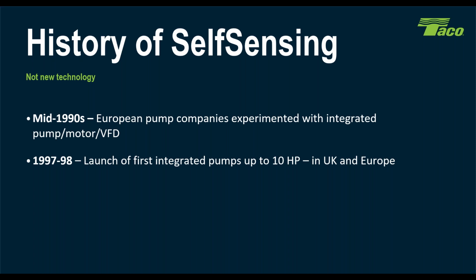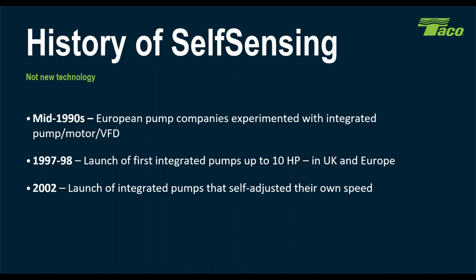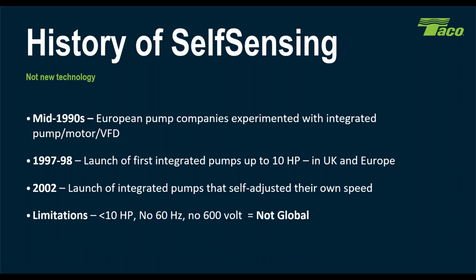So Holden Brook eventually got bought, and the company that bought them brought the technology here to North America, and that was in 2002. This is when it was launched into North America, in 2002. And that included pumps with unit-mounted drives that had all the self-sensing capability built into them, so we were no longer required to have a pressure transmitter out in the system to tell the pump what speed to run at. So as you can see, it's been around for a very, very long time. This is not new technology.